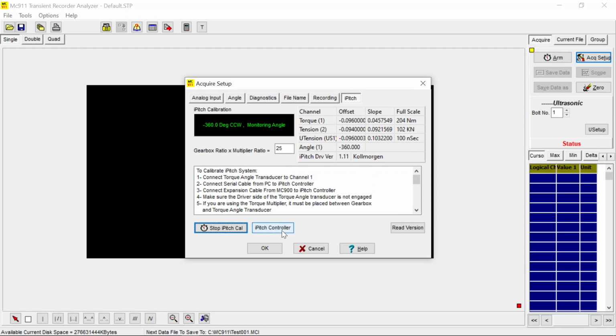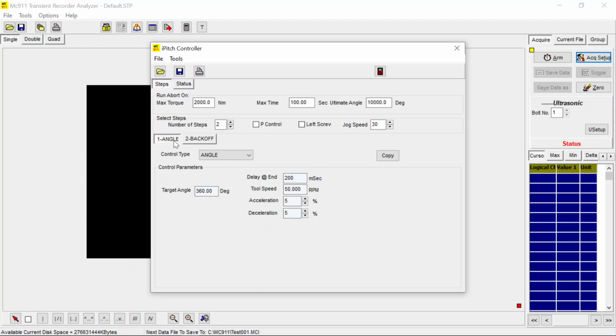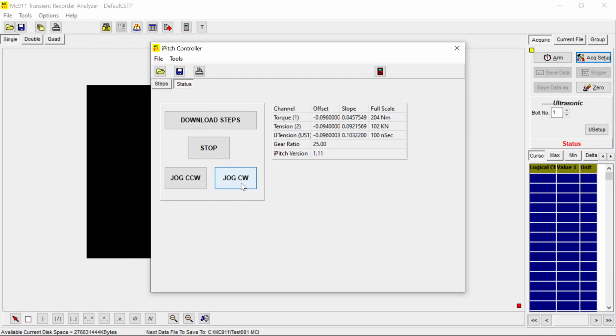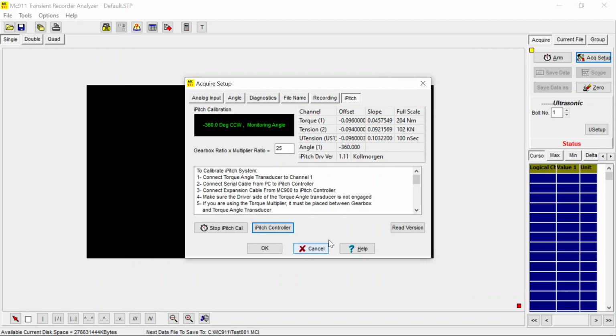So in here we have the iPitch controller button. It's not used for any programming at this point. You can use it for jogging left or right if you want to use it for adjusting the bolt. That's all it is for. Basically, this is it for this section. Let me, at this point, attach the load cell with bolt to the torque angle transducer.